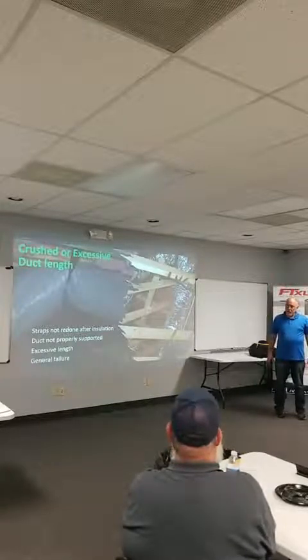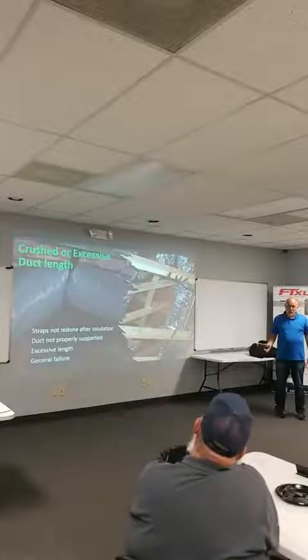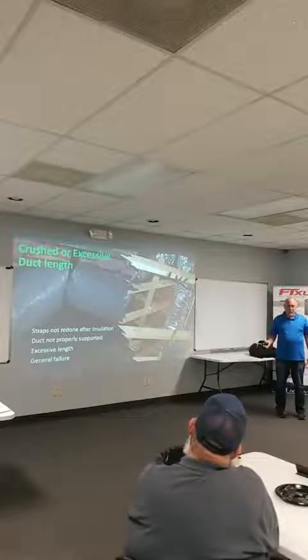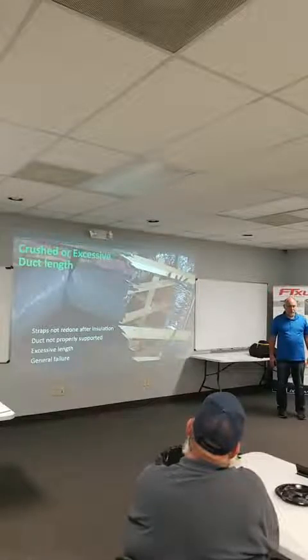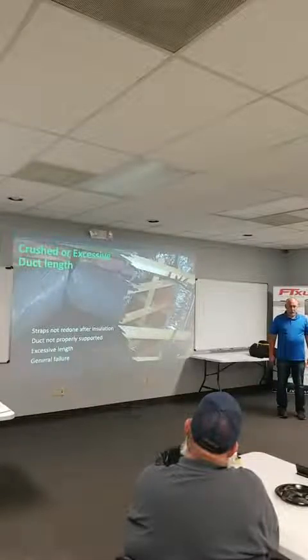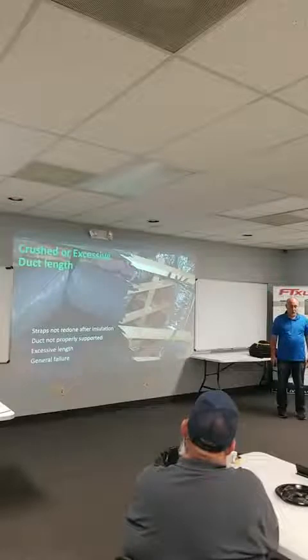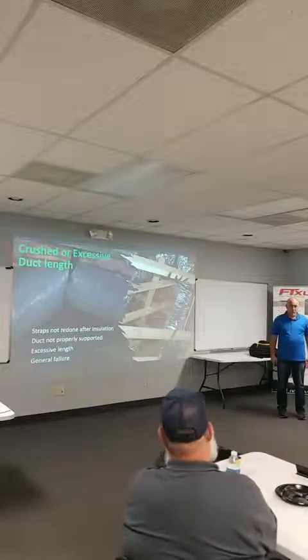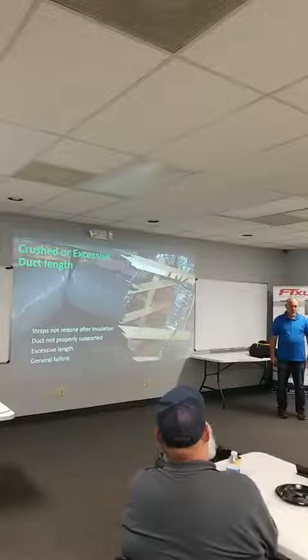And I'm up there, and I'm like, well, Measurequick's saying you got really high airflow. And he's like, no. He goes, we checked the airflow. In fact, it's set at 350 CFM a ton. I'm like, well, I'm telling you, software doesn't lie. You got high airflow. And he's like, I don't think so. And I'm like, well, let me just check your dip switch settings, ECM motor. So I go in there, sure enough, he's got it set for 350 CFM per ton, and 3-ton condenser, but they never changed the blower speed. It's set for 5 tons from the factory. So they're running 350 CFM per ton on a 5-ton system, right?